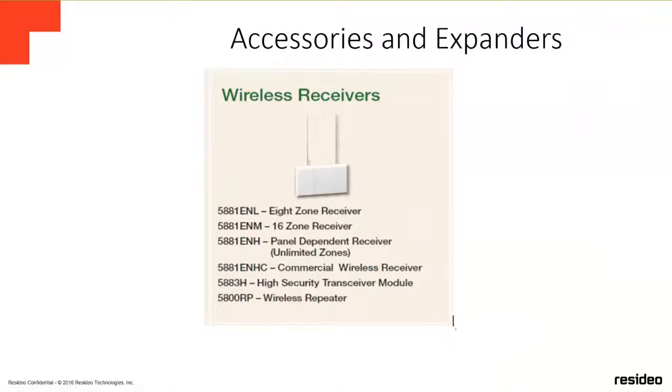For wireless receivers we have the 5881 in L, M, and H versions — L supports 8 wireless zones, M supports 16 wireless zones, and H supports up to all wireless zones the panel supports. We also have the 5881ENHC commercial wireless UL receiver behaving as a high receiver, the 5883 high security transceiver module for bi-directional devices like wireless keypads, wireless relays, and wireless sirens, and the 5800RP wireless repeater. The repeater will repeat signals from the receiver only, not from another repeater.